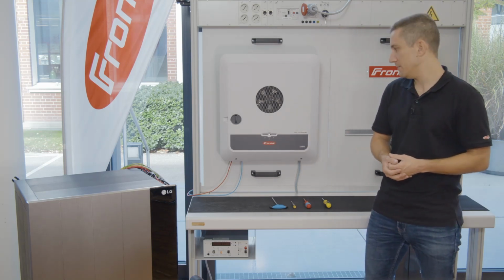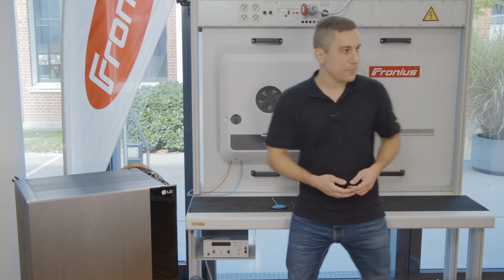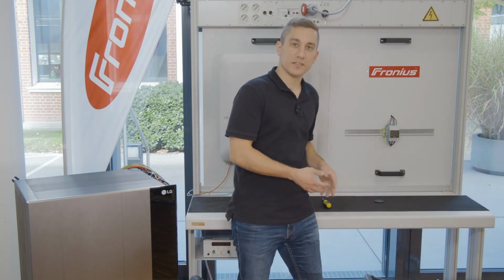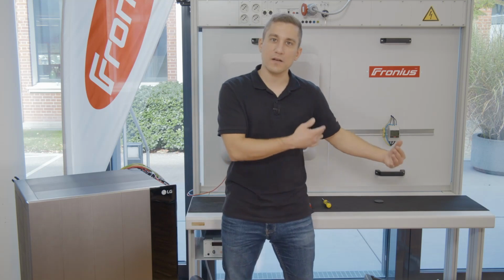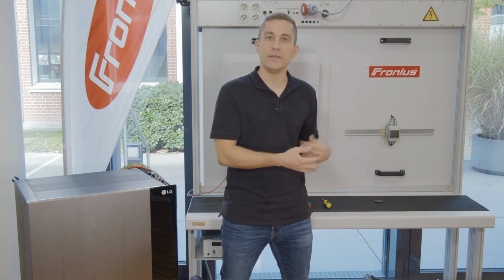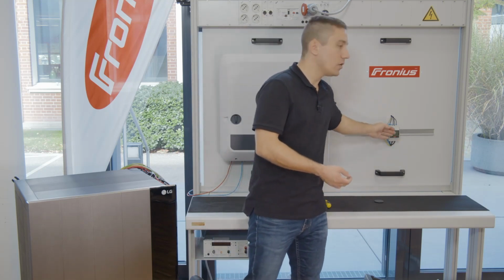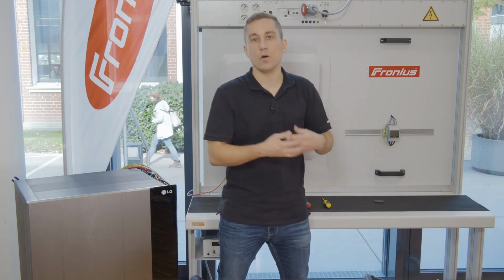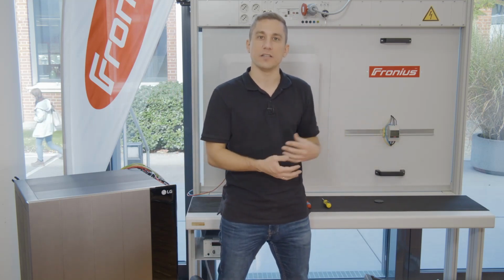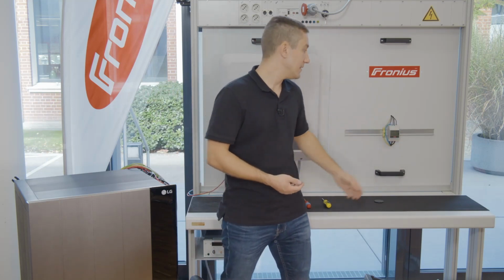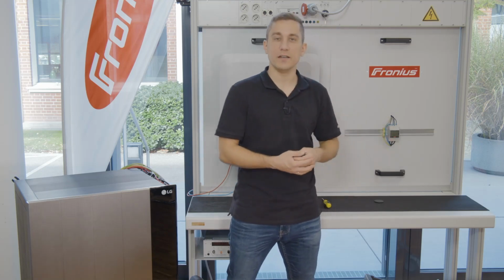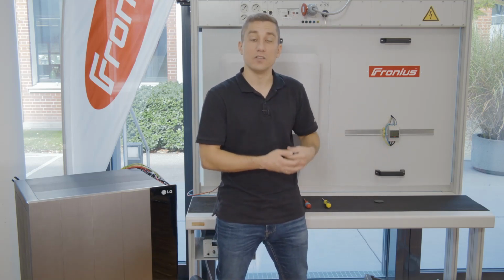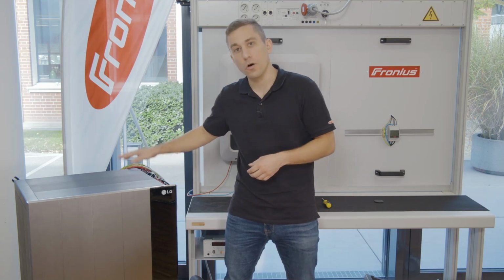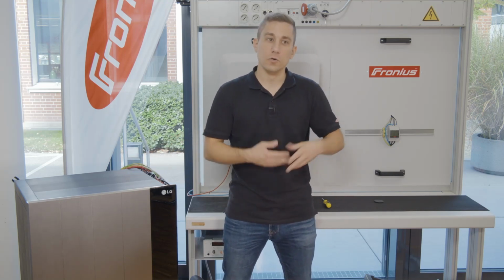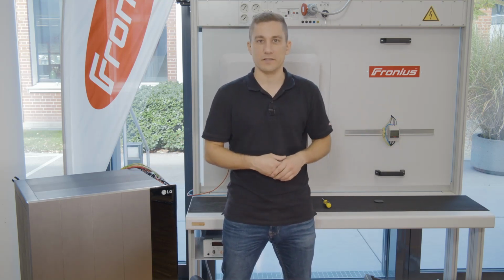And third, we have of course our Fronius smart meter, which is our bidirectional meter, and we use that to get all the energy measurements and all the energy flows within the system. So with the help of the data of the Fronius smart meter, the Fronius GEN24 Plus knows when to charge or discharge the battery to keep an optimal performance.